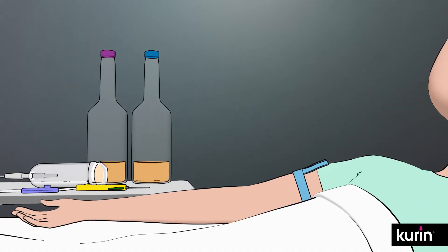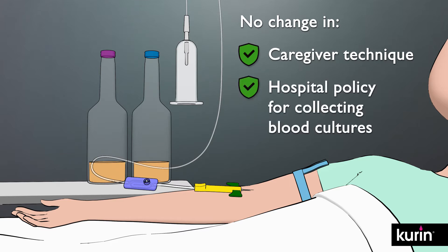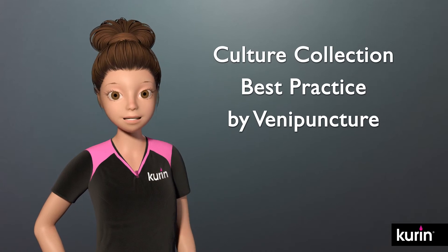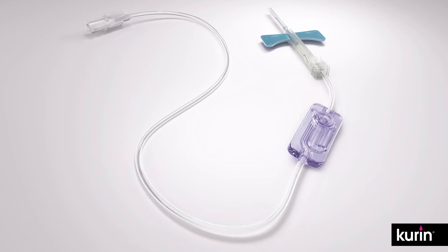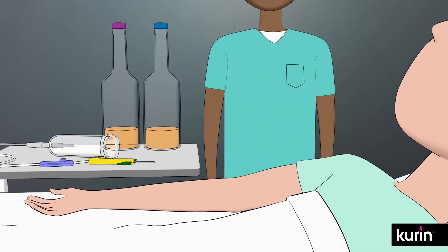Fortunately, Kurin's passive solution requires no changing caregiver technique nor hospital policy for collecting blood cultures. The Kurin Butterfly Set is 12 inches long and has a total discard volume of approximately 0.74 milliliters, including about 0.15 milliliters within the Kurin lock.